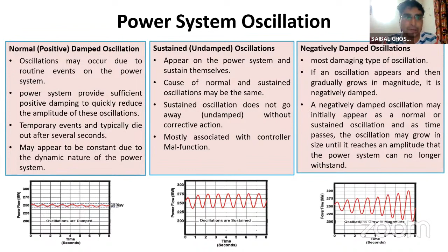The oscillation will be magnified over time. Now, how is the oscillation frequency determined? This is basically linked to the mass of the synchronous generators which are oscillating against each other. If we talk about single generator oscillations, then its own mass will determine the frequency. But for inter-area oscillation, how the group is formed matters, whether in the group there are 2 generators or 30 or 50, the overall inertia of that group will determine the oscillation frequency.